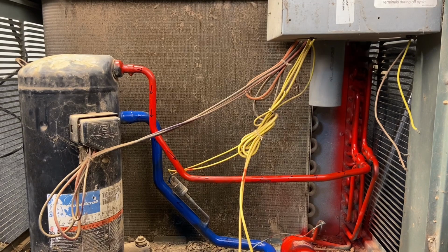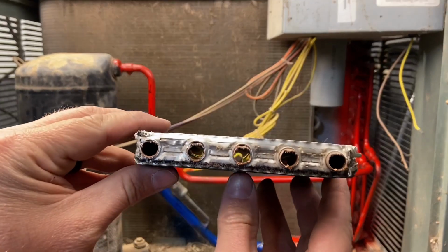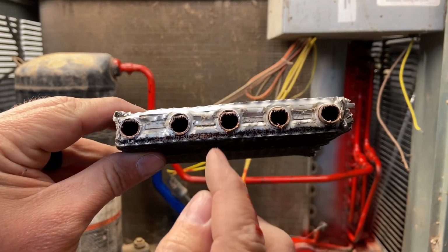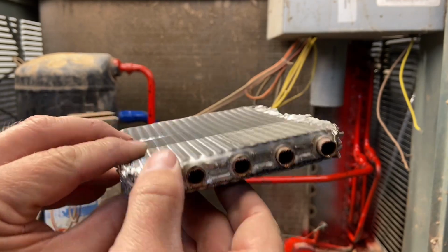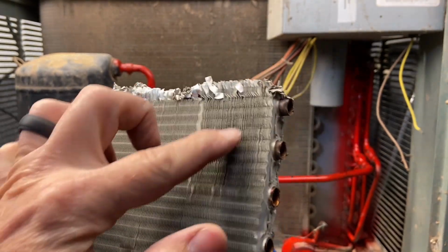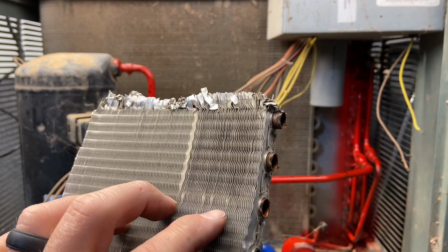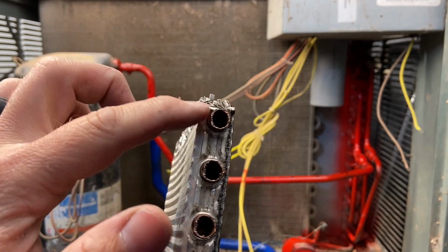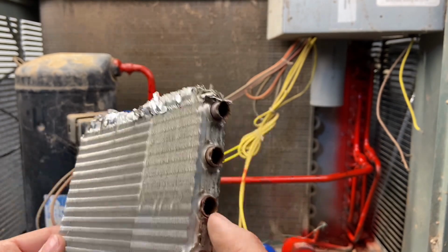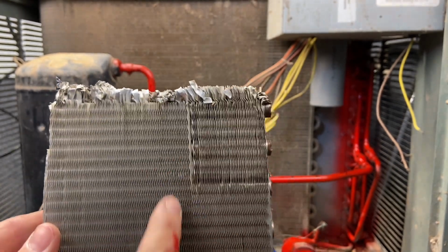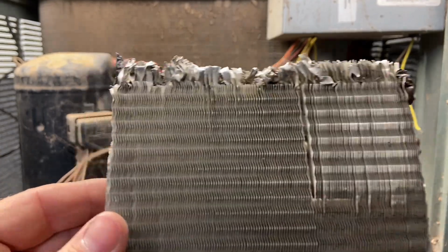There's many different kinds, but here we can see we got one that's cut open, and you actually see the tubes inside here. These tubes are where the refrigerant runs, and due to the second law of thermodynamics, we have lots of different surface area here, and it's made of a heat transfer material such as aluminum. So we have a lot of refrigerant going through a lot of tubes, and a lot of these tubes touching a lot of aluminum. This increases heat transfer, and these fins are very, very close together.